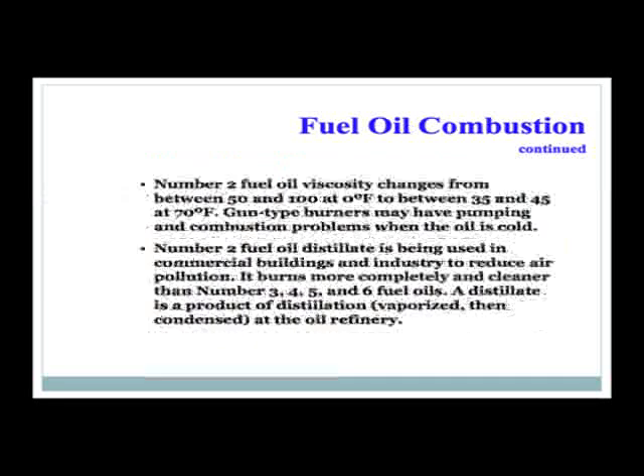Number 2 fuel oil viscosity changes between 50 and 100 at zero degrees to between 35 and 45 at 75 degrees. Gun-type burners may have pumping and combustion problems when the oil is cold.